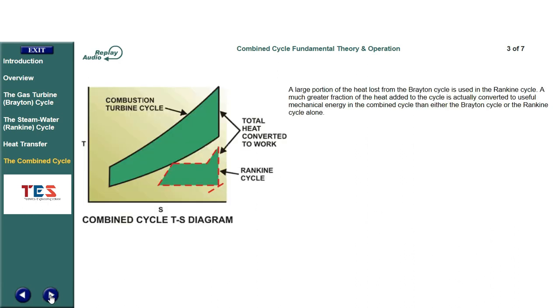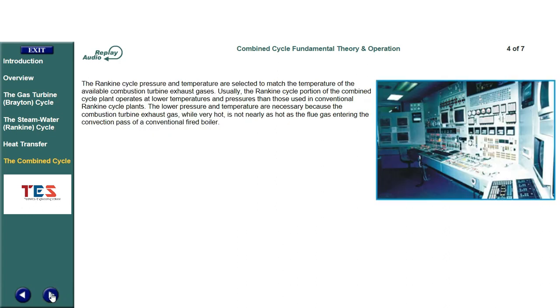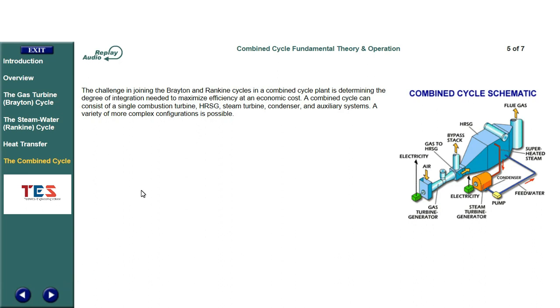A large portion of the heat lost from the Brayton cycle is used in the Rankine cycle. The Rankine cycle pressure and temperature are selected to match the temperature of the available combustion turbine exhaust gases. Usually, the Rankine cycle portion of the combined cycle plant operates at lower temperatures and pressures than those used in conventional Rankine cycle plants. The lower pressure and temperature are necessary because the combustion turbine exhaust gas, while very hot, is not nearly as hot as the flue gas entering the convection pass of a conventional fired boiler. The challenge is determining the degree of integration needed to maximize efficiency at an economic cost.